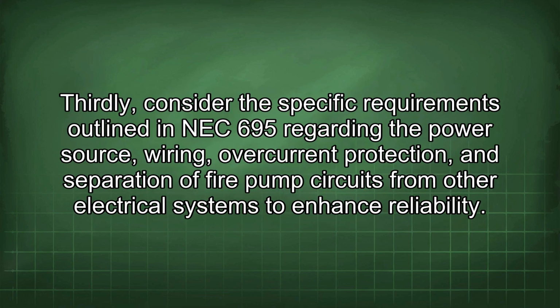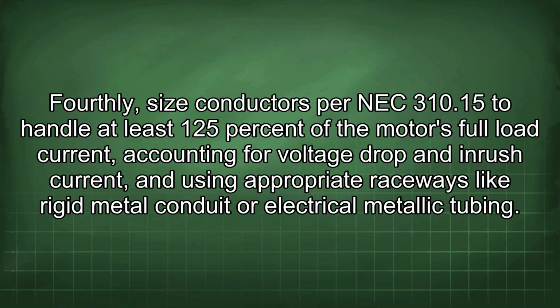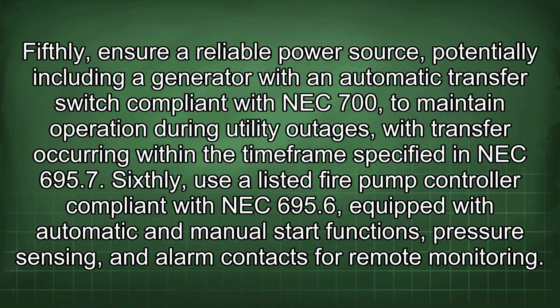Thirdly, consider the specific requirements outlined in NEC 695 regarding the power source, wiring, overcurrent protection, and separation of fire pump circuits from other electrical systems to enhance reliability. Fourthly, size conductors per NEC 310.15 to handle at least 125% of the motor's full load current, accounting for voltage drop and inrush current, and using appropriate raceways like rigid metal conduit or electrical metallic tubing. Fifthly, ensure a reliable power source, potentially including a generator with an automatic transfer switch compliant with NEC 700 to maintain operation during utility outages, with transfer occurring within the time frame specified in NEC 695.7.